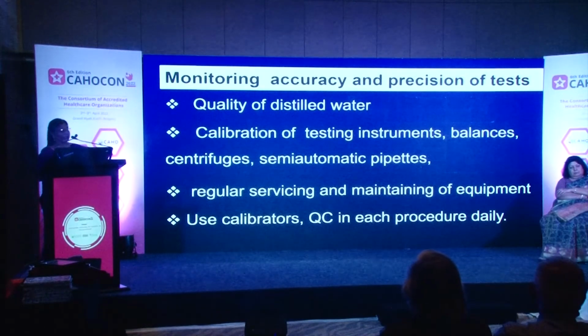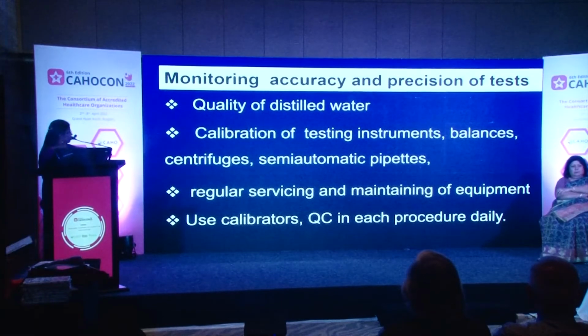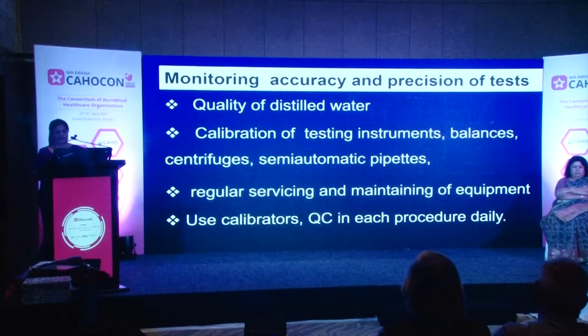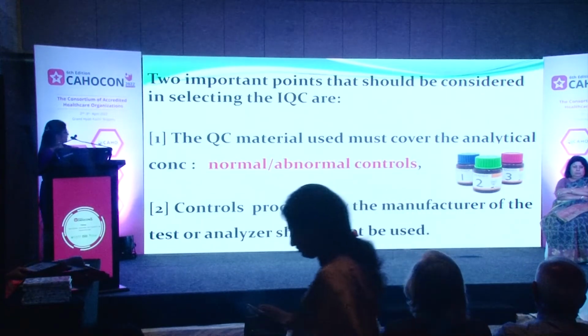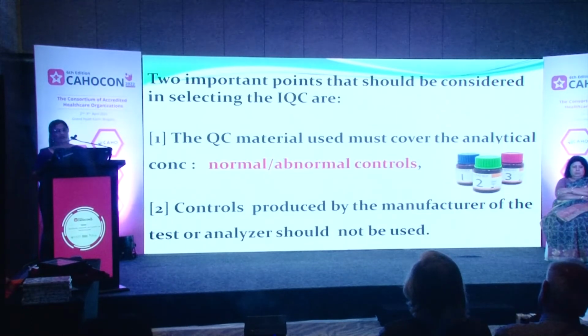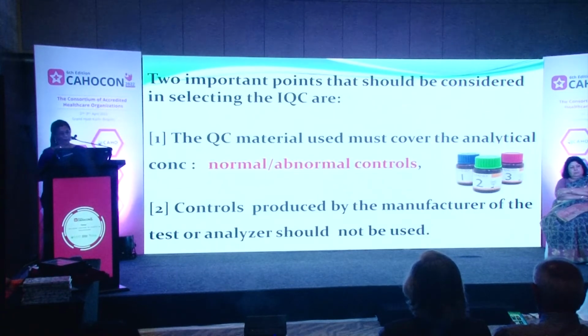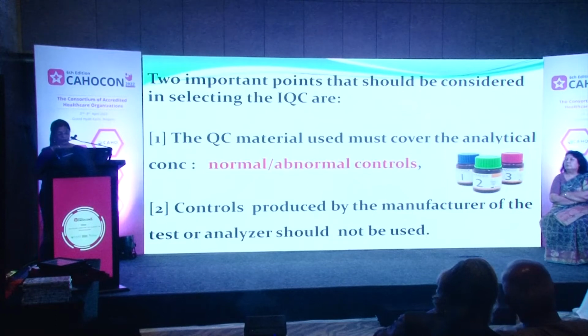In a laboratory, you need to monitor the quality of distilled water, calibration of testing instruments, balances, and all those items that are required for testing of the sample, regular servicing, maintaining of equipment, use of calibrators and QC in each procedure daily. There are two important points that should be considered in selecting the IQC. The IQC material must cover the analytical concentration, normal and abnormal control.